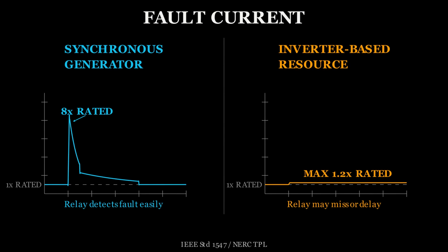Inertia is the first thing a retiring gas plant takes with it. Fault current is the second. When there's a short circuit on the transmission system, a line falls, insulation fails, lightning strikes, voltage collapses at that point.